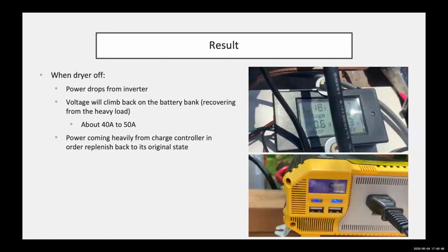When we turned the dryer off, we noticed the power dropped from the inverter and the voltage came back up, recovered from the battery bank after the heavy load. Because the controller was heavily charging power, it was able to compensate for the loss and return the system back to its original state.